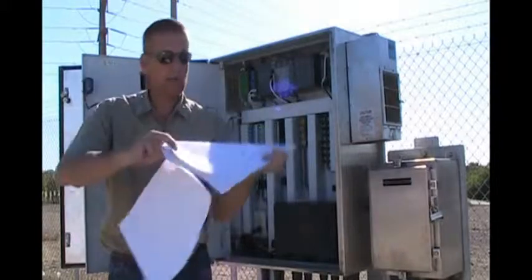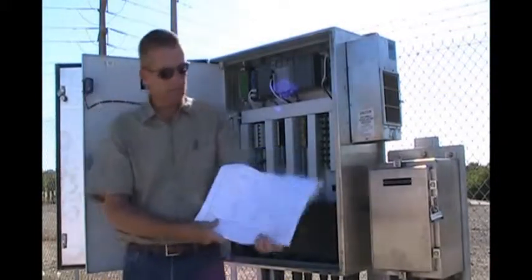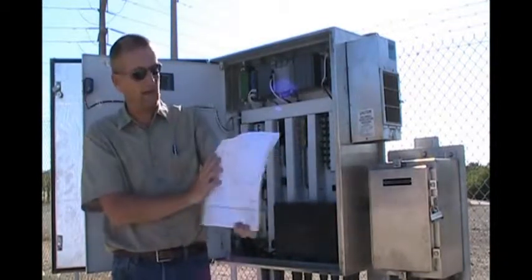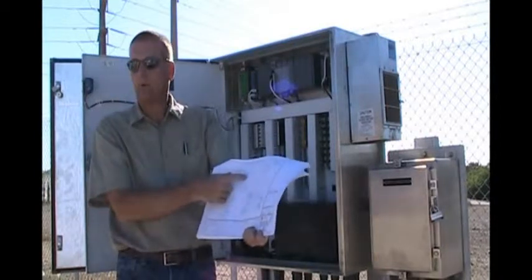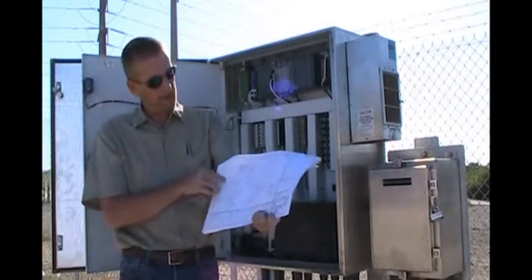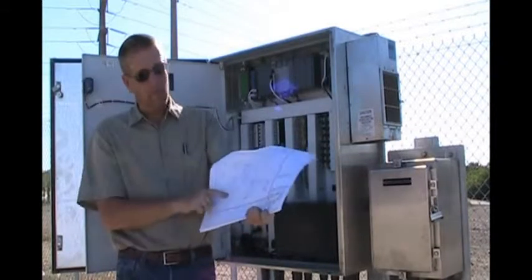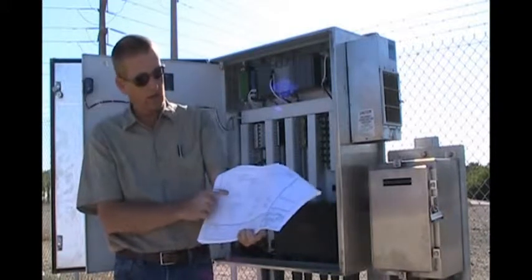Now for the loop drawings, we have the same thing. This is a loop drawing of LT 2005. So the level transmitter comes into the wireless IO panel 2005, shown here. It gives you the wiring, wire numbers, but then it goes to radio. So I've included the radio in the loop drawing, so you know there's a radio there.